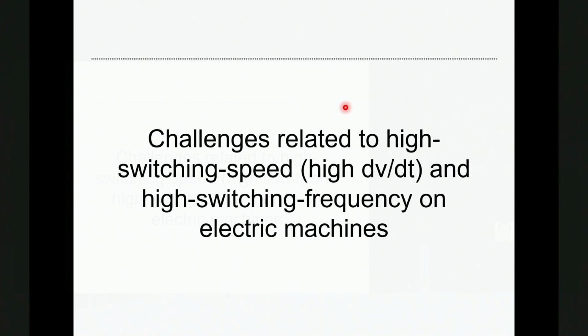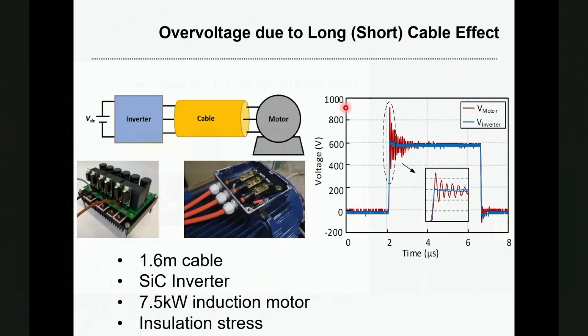There are also challenges related to the fast switching speed and high switching frequency. One of the main challenges is the motor over voltage due to the high frequency operation. This is not a new thing. Even in silicon IGBT based converters, you will see high over voltage at the motor terminal if there is a long cable between the inverter and the machine. But for a silicon carbide converter with very fast switching, even a short cable can lead to over voltage at the motor terminal. In this case, we have shown a 1.6 meter cable length, where you can see the inverter output voltage is 600 volts, but the motor terminal voltage has reached 900 volts, almost 50% over voltage.